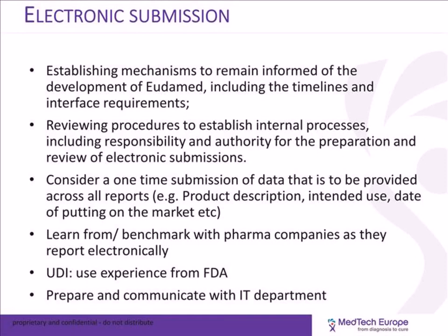And our internal procedures within each manufacturer need to be established. They should include the responsibility and the authority for this electronic submission: who will have authority to open the EUDAMED section, who will file them, who will prepare them. So there is a new area of procedure and responsibility that we did not have before, which will have to be considered.